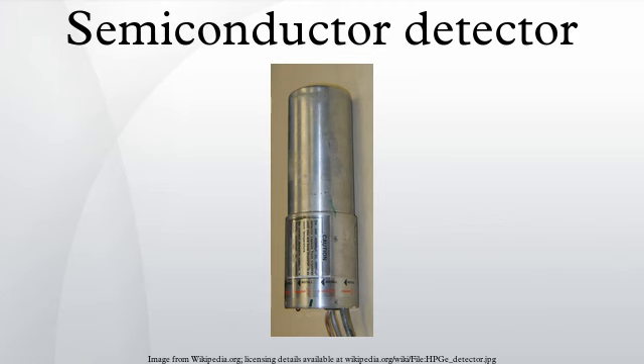As of 2012, HPGe detectors commonly use lithium diffusion to make an N-plus ohmic contact, and boron implantation to make a P-plus contact. Coaxial detectors with a central N-plus contact are referred to as N-type detectors, while P-type detectors have a P-plus central contact. The thickness of these contacts represents a dead layer around the surface of the crystal within which energy depositions do not result in detector signals. The central contact in N-type detectors is opposite to the surface contact, making the dead layer in N-type detectors smaller than the dead layer in P-type detectors. Typical dead layer thicknesses are several hundred micrometers for a lithium diffusion layer, and a few tenths of a micrometer for a boron implantation layer.